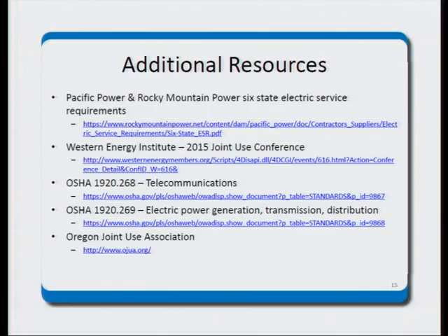Also, to follow up on his question, secondary poles, no distribution on top, that's the type of pole we can go ahead and do without permission, for a service drop. Yes. Yeah, could you actually repeat that? You could actually attach a service drop to any distribution pole. It doesn't have to be just what we call a service pole. Any distribution pole, you could make an attachment of a service drop and then submit the application after.